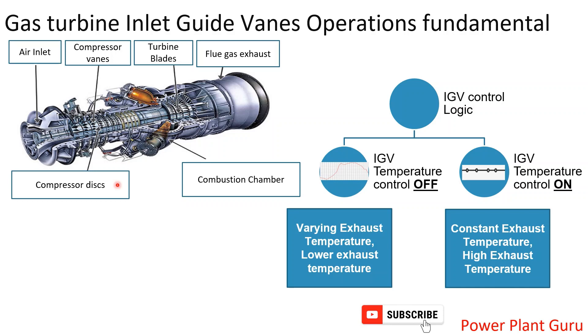In temperature control mode OFF, the IGV is fully open and it is not going to control the temperature. If you change the load — if you increase the load when the machine is not at full load — the temperature will increase. If you decrease the load, the temperature will decrease. This is because the IGV is already fully open, so maximum air quantity is flowing. Increasing load means increasing fuel, which increases temperature, and reducing load reduces fuel, reducing temperature.